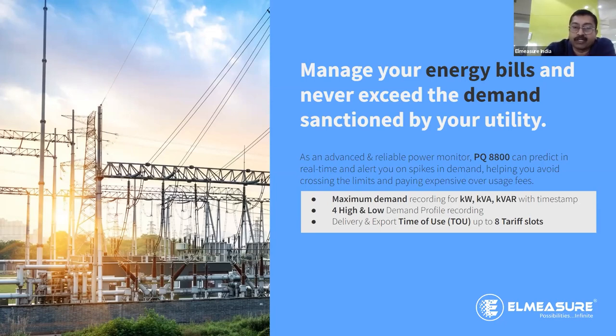So the product, in general as a standard, should be installed at the point of common coupling, which is at the incomer level. And if there are some critical feeders that they would like to monitor, especially in areas where there are drives installed, or some furnace applications or arc welding machines where the load variations are very high, in those cases this meter can be appropriately installed within the panel.